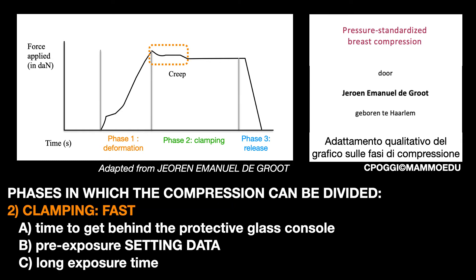The second phase, on the other hand, has to be very fast, to minimise the patient's discomfort. Remember that the radiographer has to get behind the protective glass console, and sometimes the ergonomics of the room you work in is not ideal. A pre-exposure is performed to determine the right exposure settings — choice of target filter and so on — and the exposure times are in any case long. We must shorten the clamping phase as much as possible.